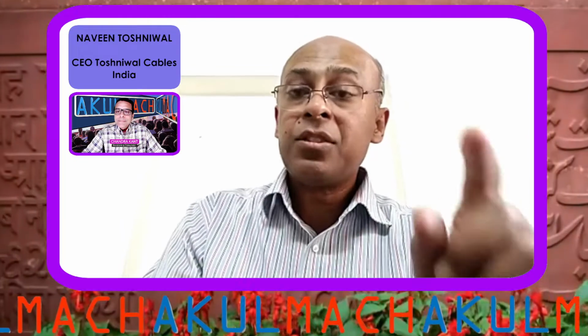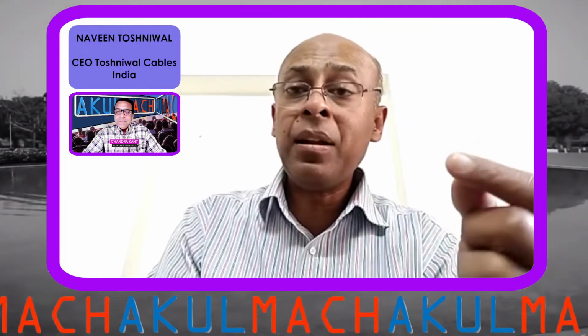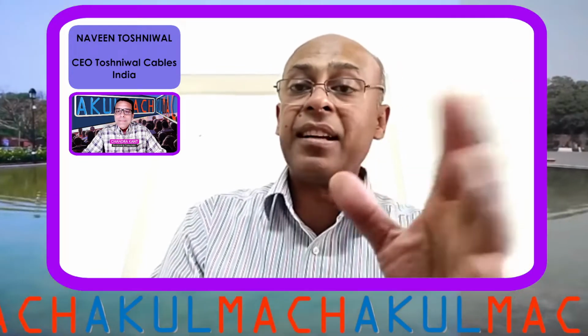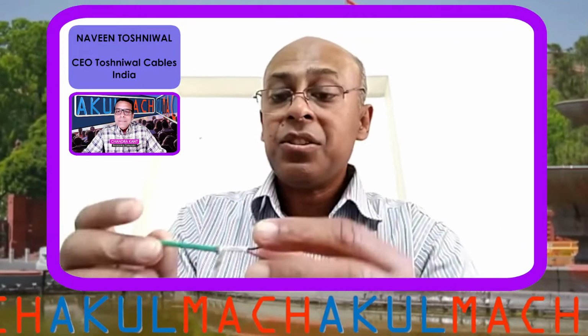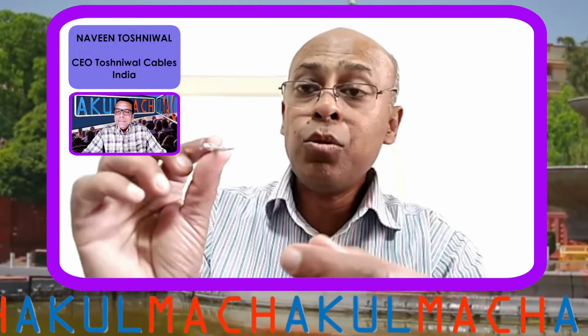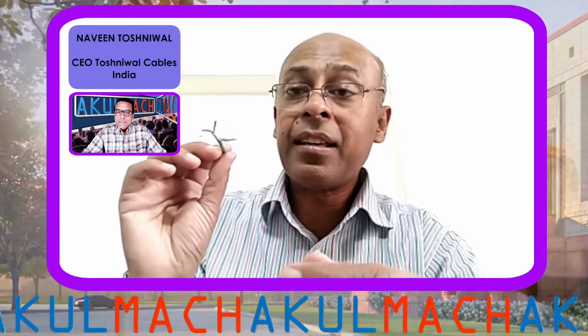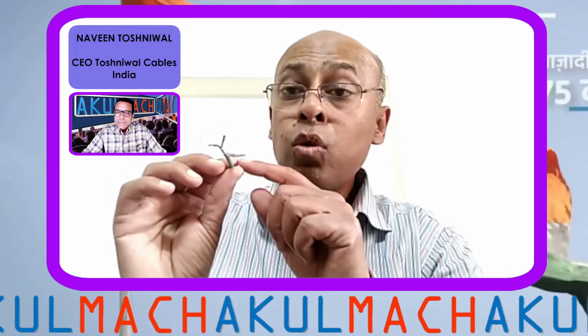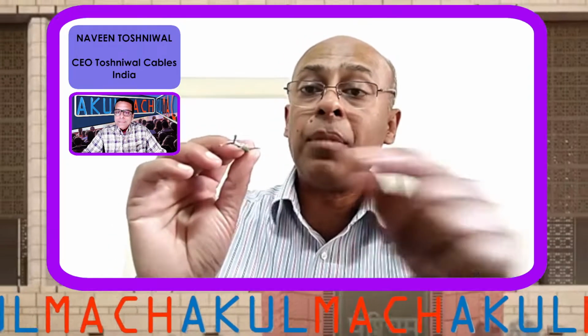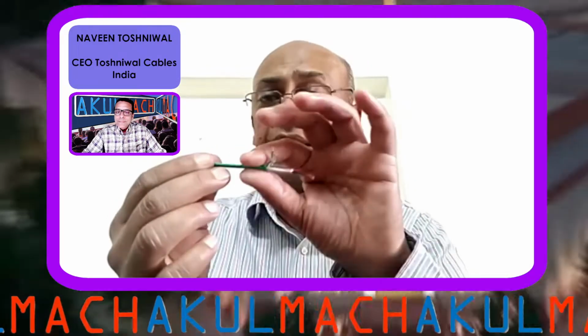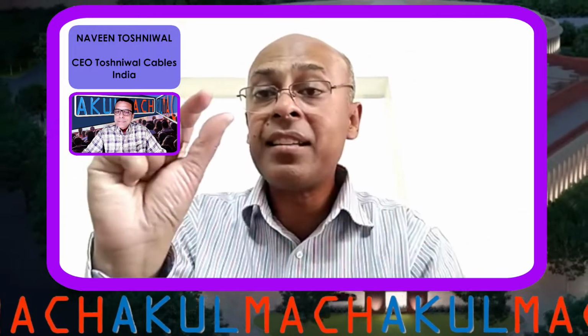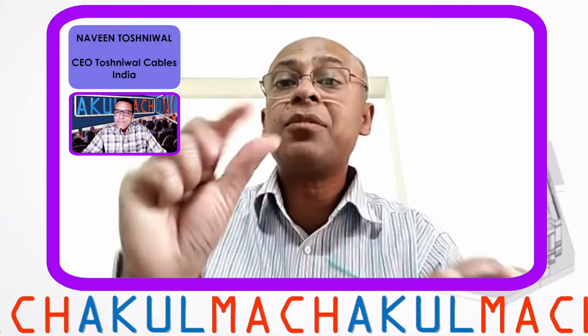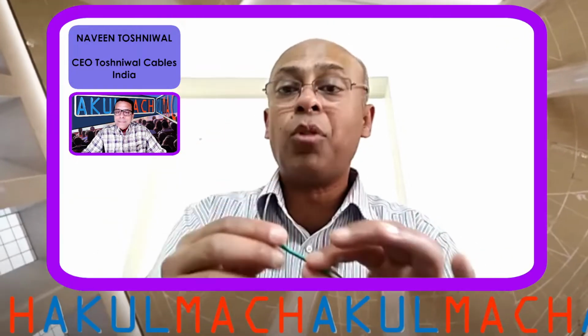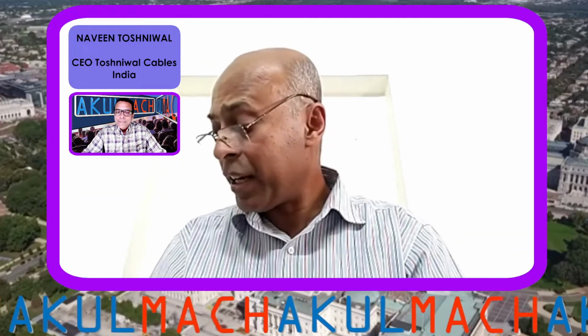So this dip type thermocouple gives the reading, and then it melts. It is dissolved in the metal. So this cable is used for putting it through the lance, which goes up to the thermocouple to transmit the reading. It is very thin so that it goes easily inside the small metallic lance, which is used for dipping in the molten metal. Now I'll show you another interesting sample.